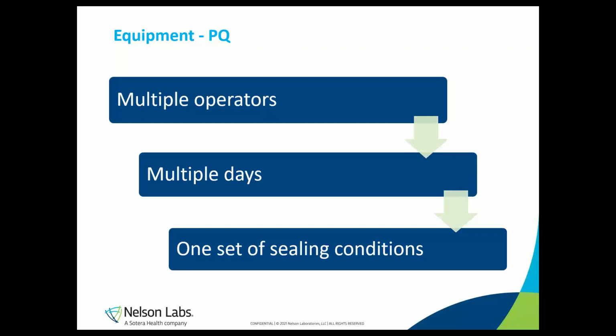Since we've already shown that the seals are continuous and sufficiently strong for the whole processing window, we will seal our samples at either the nominal or the normal production sealer settings. Or if you want to create a worst case scenario, then you would seal at the low settings. We will test the seals for seal integrity and seal strength as we did in the OQ. And if the acceptance criteria in the protocol are met, then we can write up our validation report.